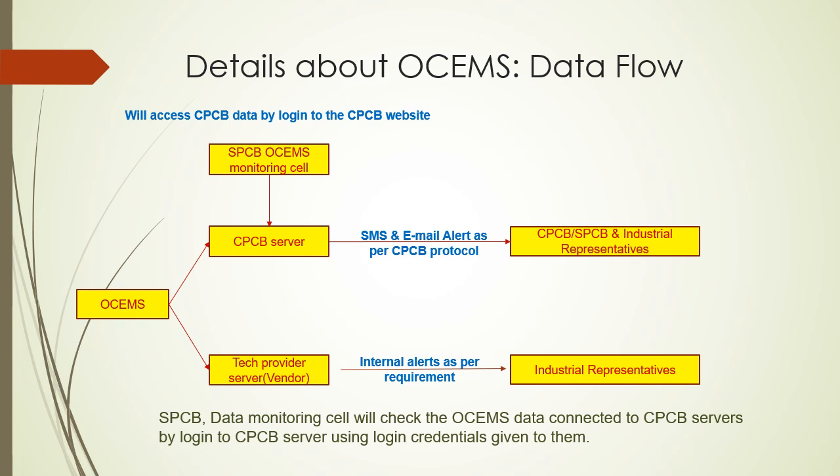So for example, if the COD limit is 50 mg per liter, and I want that in my STP, once 60% of the 50 mg per liter is reached, I should get a notification so that my team can work on it. That is, when the value is closer to the exceedance limit, I can get an alert.